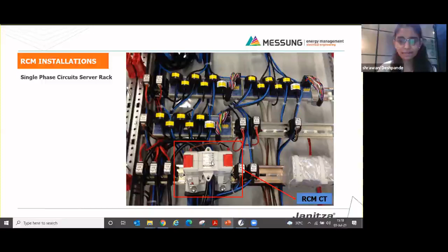Now, as I said, the residual currents are of 3 types. So to understand the types of residual current, let's take an example of a simple system in which a 3-phase induction motor is fed through a variable frequency drive. Now, if my fault or insulation failure occurs within this region, meaning before the variable frequency drive, then my residual current would be of type A.